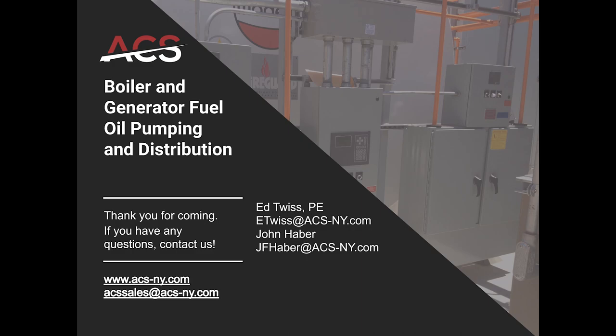Yeah. Steve asks, can you get a belly tank with only the New York City tank 25 PSI tag? I've only seen belly tanks with a 25 PSI tag and a UL 142 tag, and therefore inspectors require the belly tank to be vented as if it were a 142 tank. This is a very good question.